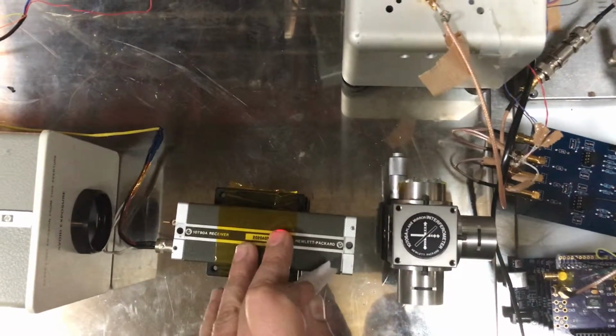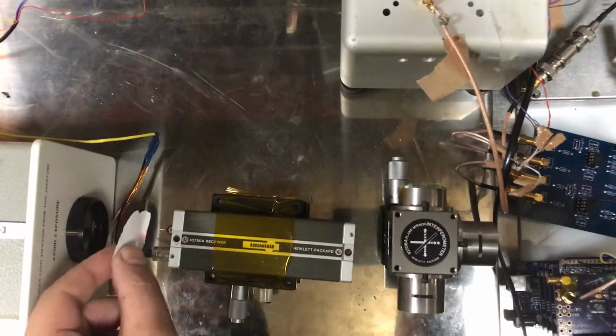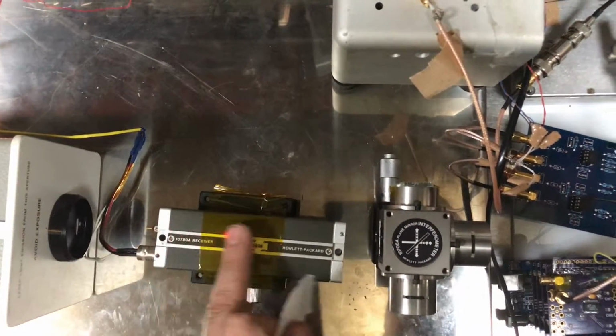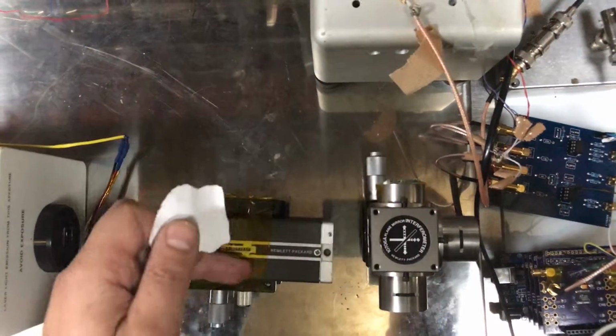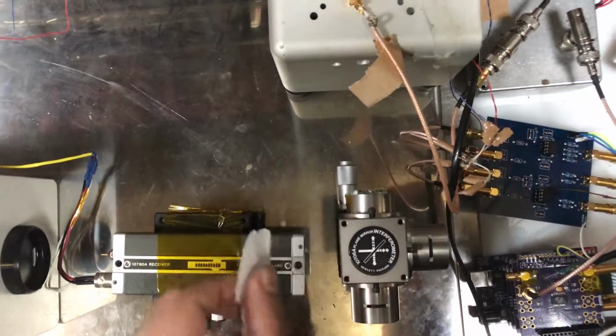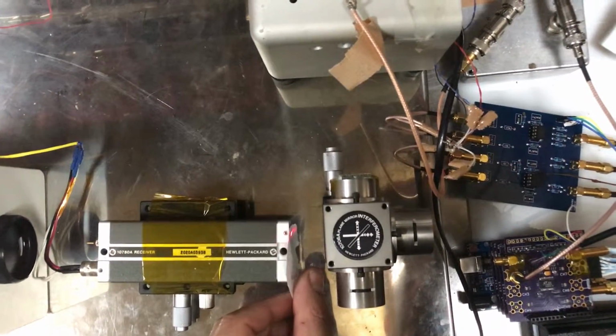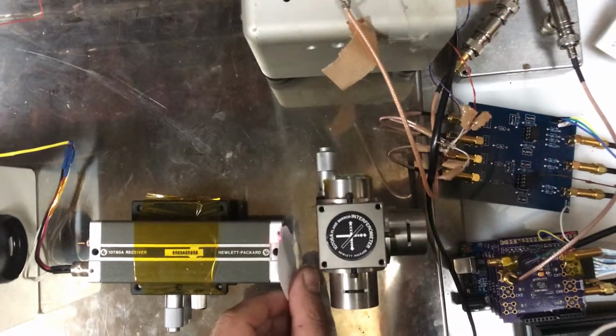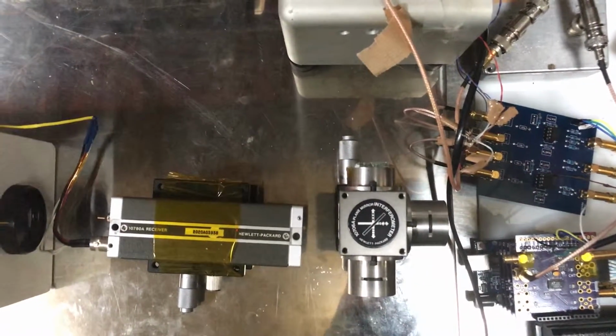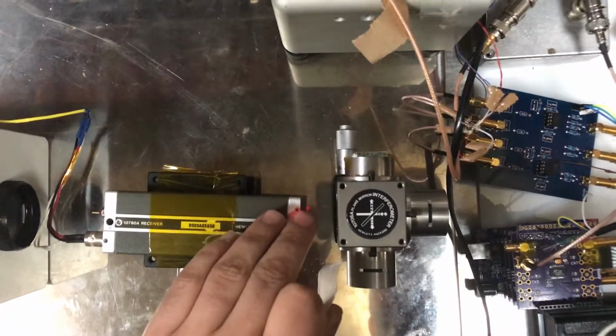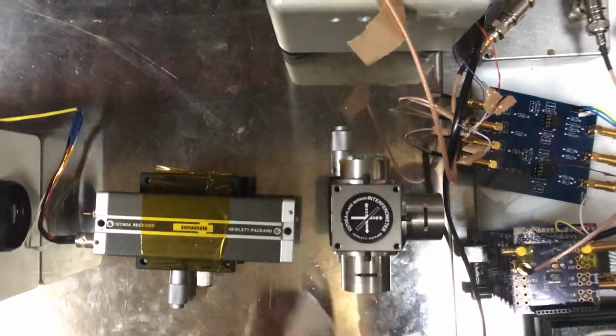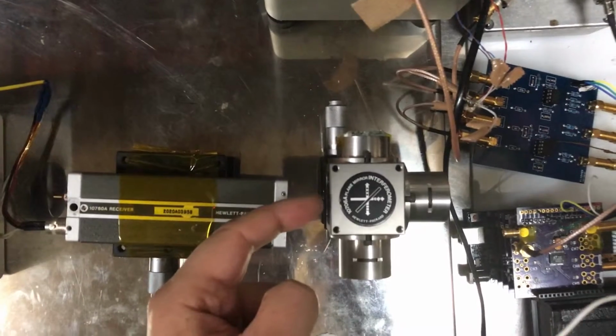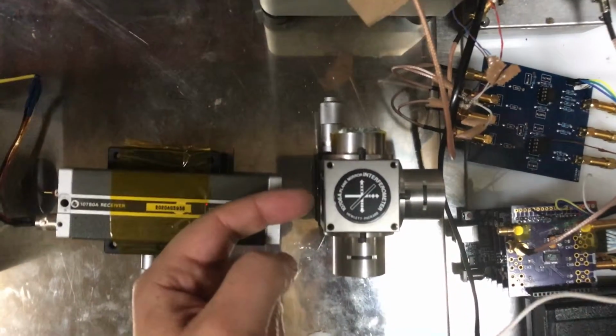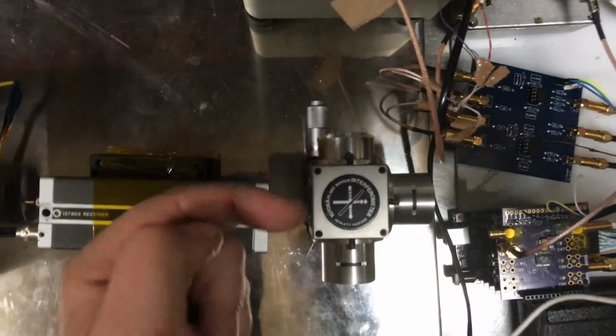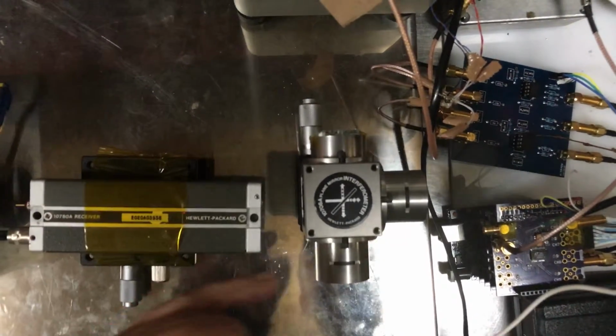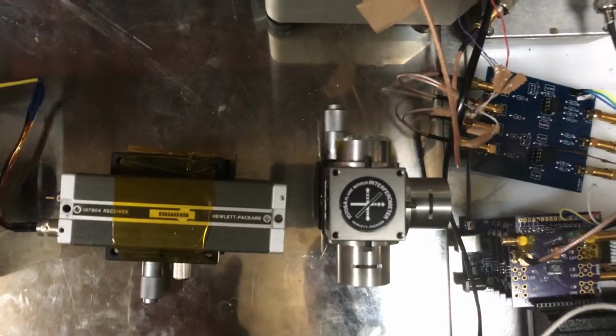You need to have the photodiode such that the laser just comes across the top here, and then it bounces through. So there's not much clearance between these two beams, right? It's less than a centimeter maybe. So you need to get those aligned. This hits the interferometer fairly high up, and then the output beam comes out lower down. That's the basic idea.